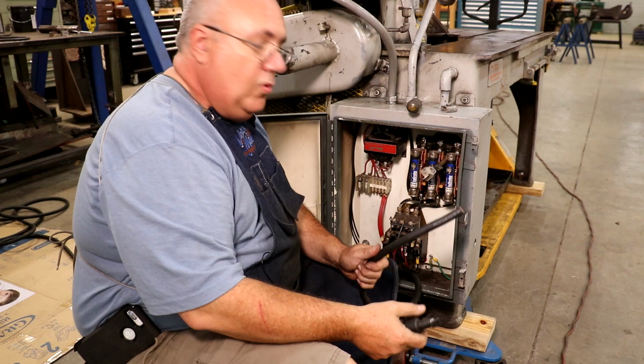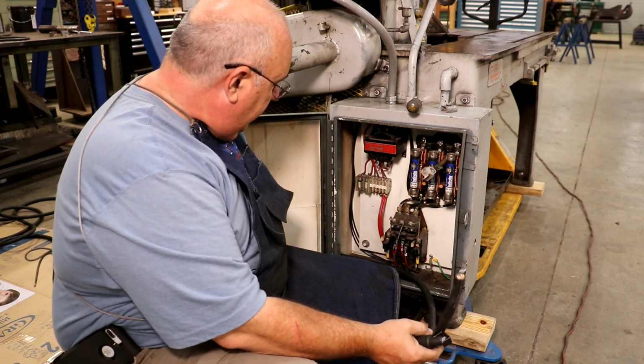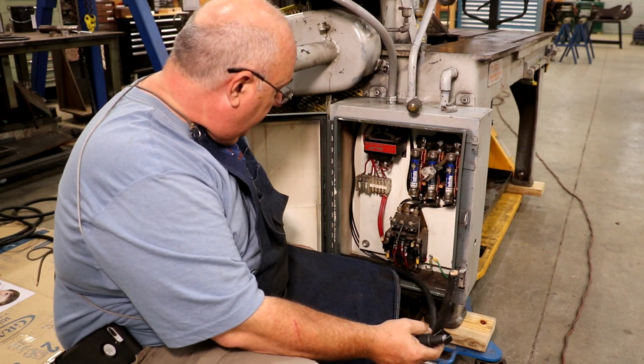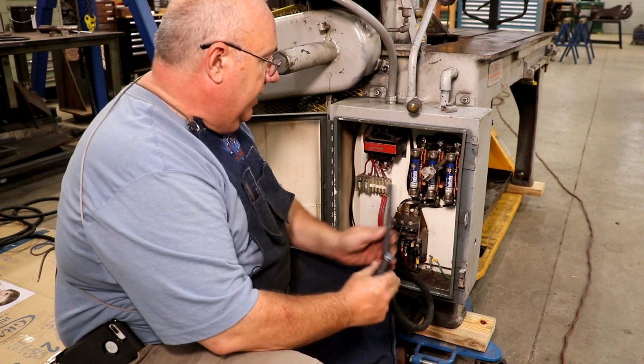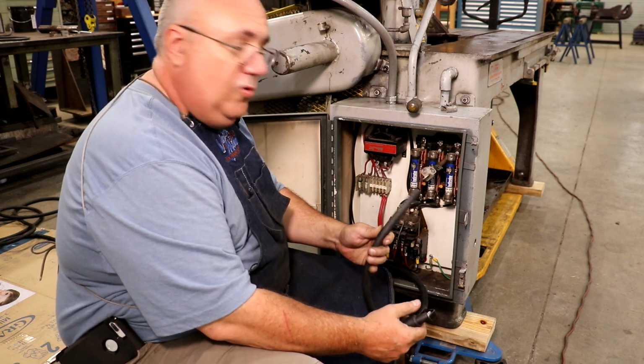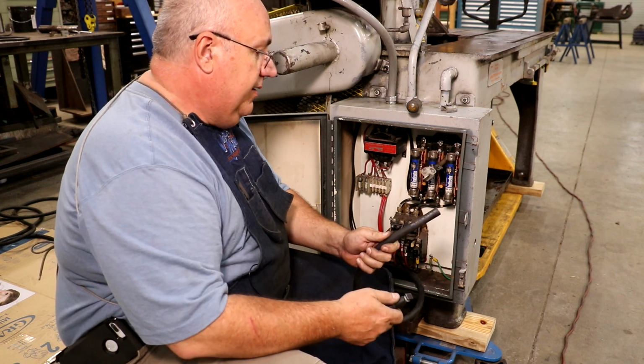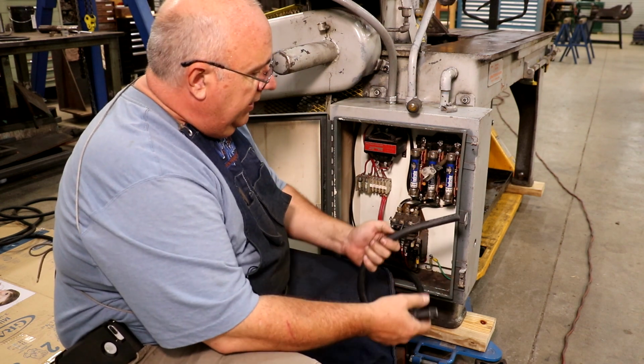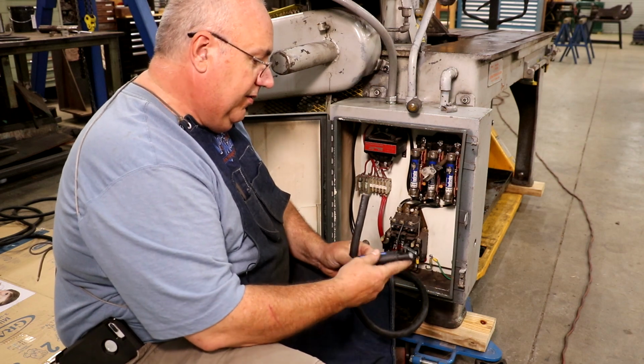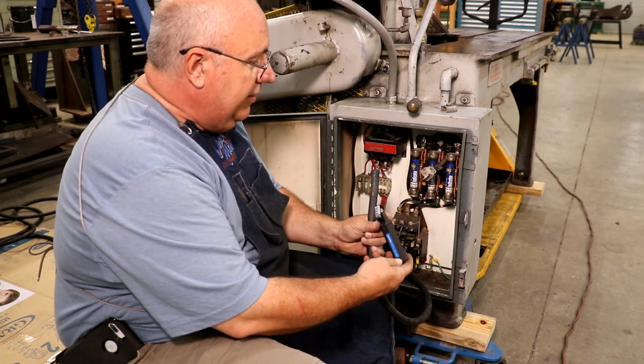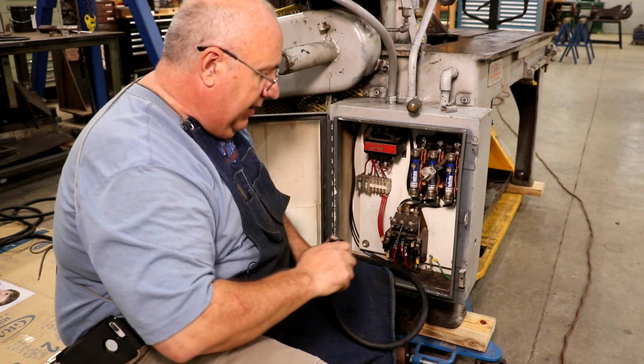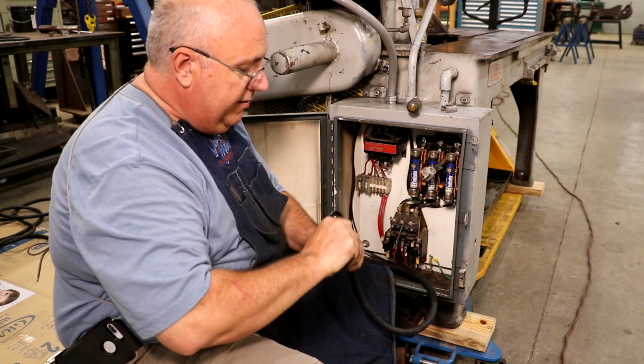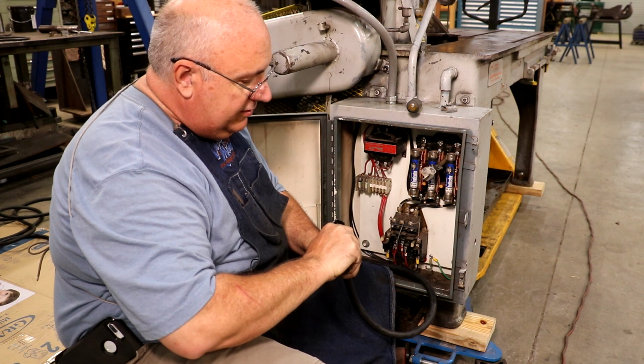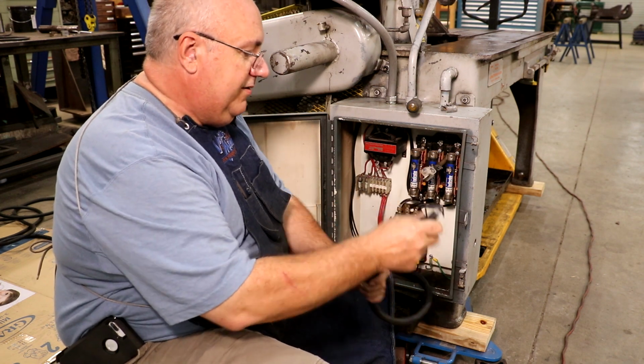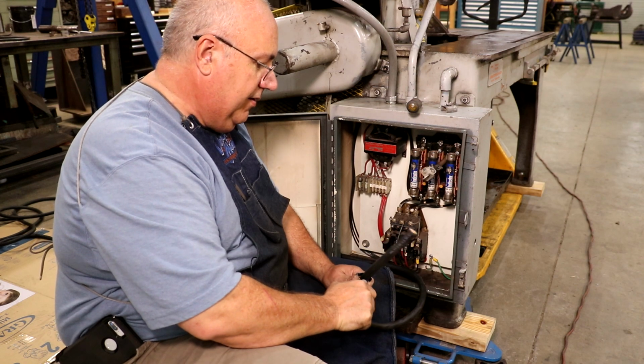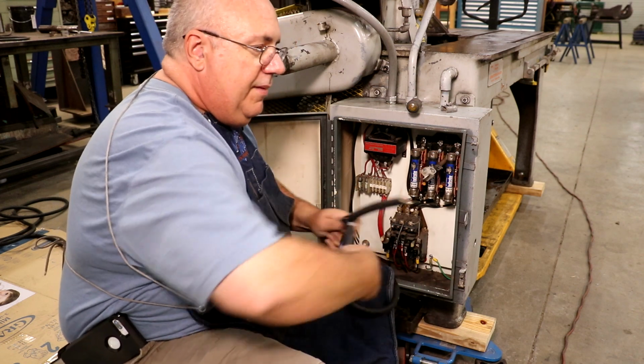So I've got my cord coming into the machine now. We came in an existing conduit fitting over here, and this is a brand new SO cord or service cord with 4 wires in it, and I need to pull back the insulation on the outside. Now I've got one of these cool wire stripping tools that makes this easy. Basically there's a little knife in here and you adjust it so it's just the thickness of this outside material. You clamp this on and strip off about that much.